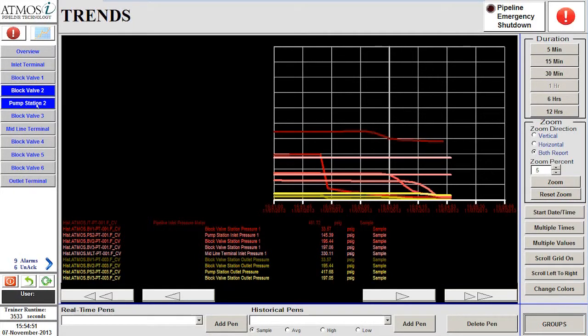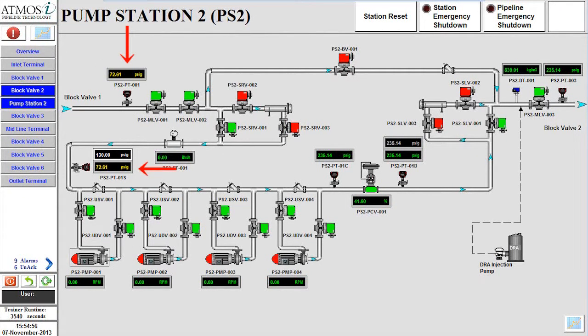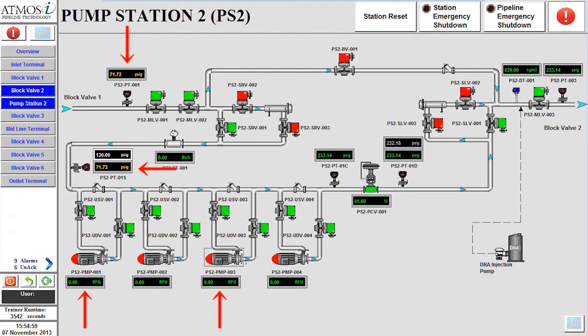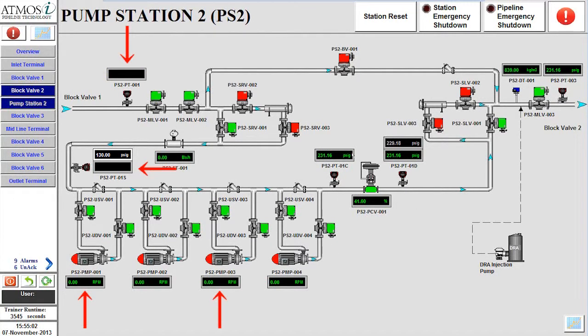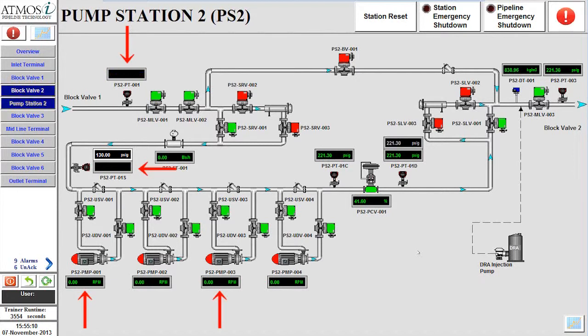Another alarm is now generated at pump station 2. Navigating to the screen, we will notice that the alarms are due to low pressure and the pumps have turned off. All these events should be of great concern, as no additional operations have occurred on the pipeline that would cause the overall line pressure to decrease so rapidly.